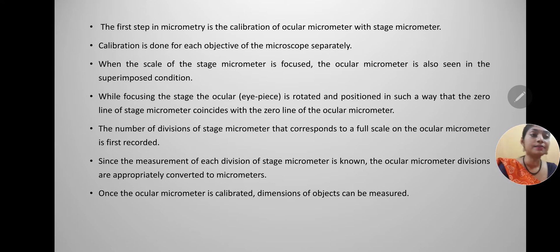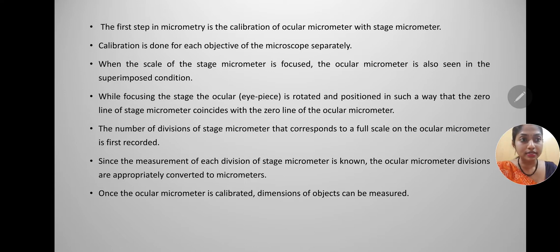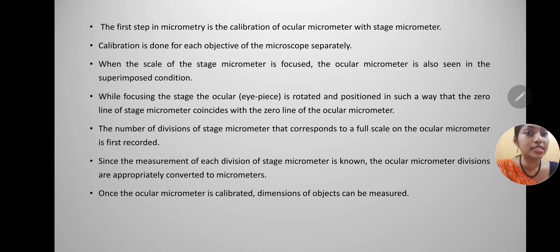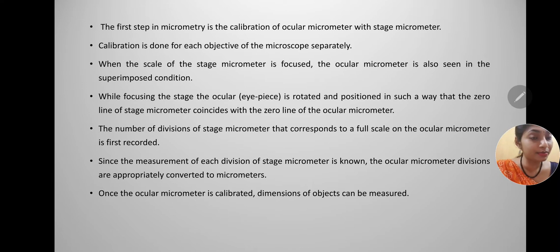We have a calibration factor formula wherein we obtain the calibration factor. Since the measurement of each division of the stage micrometer is known, the ocular micrometer divisions are appropriately converted to micrometers. Once the ocular micrometer is calibrated, the dimensions of objects can be measured.